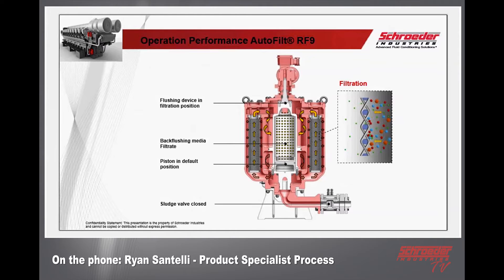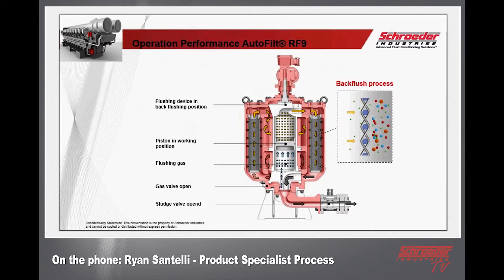On the very top you see a flushing device in filtration position — that arm stays in one position just like a gear motor drive shaft — and the sludge valve is closed on the very bottom. When in motion to back flush, the piston moves to its working position, slowly moving up and gradually passing through each filter element as it back flushes, then returns back down and moves to the next element. The flushing device moves to the flushing position, air pressure is pushed on the bottom to help lift the piston, and the gas valve opens to fill up the piston from underneath.